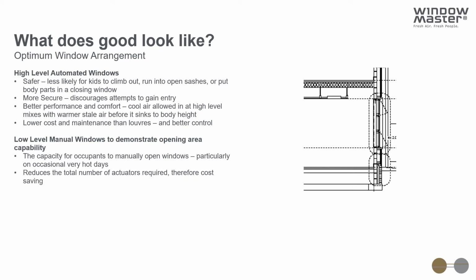We can also better control the impact of drafts when vents are at high level. We've done lots of studies which demonstrate that very acute control of vents at high level brings air in at the hottest part of the room and mixes it at a good depth into the room before it falls to body height, reducing drafts local to the window, as opposed to larger openings at low level, which can definitely introduce drafts and have to be avoided wherever possible.